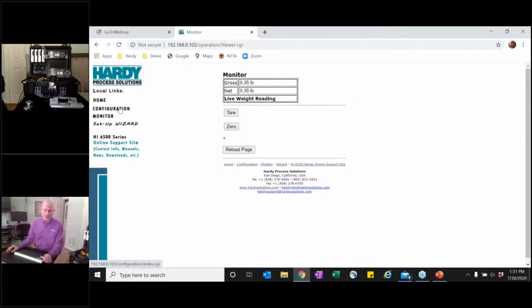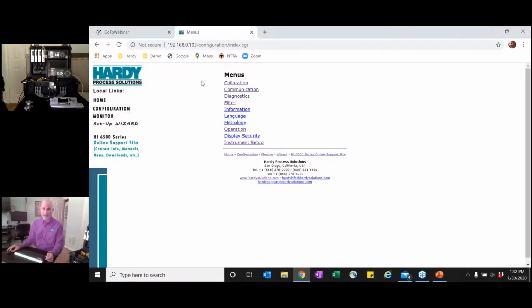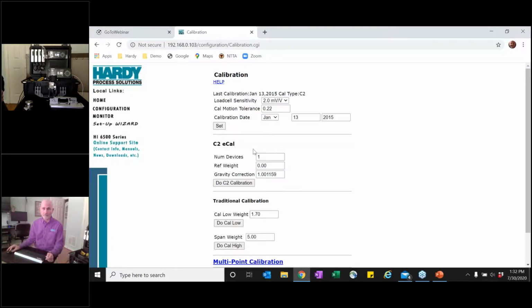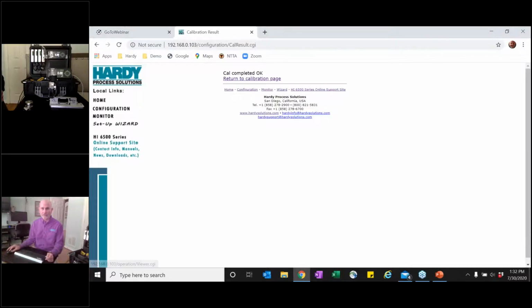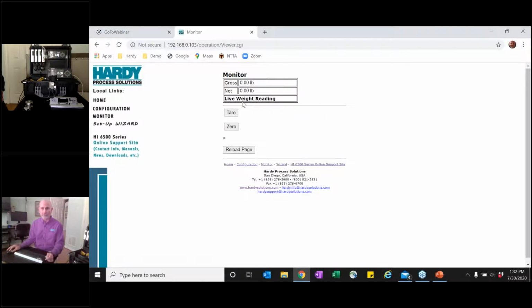So if I'm weighing the material in a tank and I've got the scale under the tank, I don't really want to know what my tank weight is. I want to know what the material weight inside. So let's go back to the calibration. And with this on there, we still have a reference weight of 0. And let's do the C2 calibration. It says it's complete. Back to monitor.